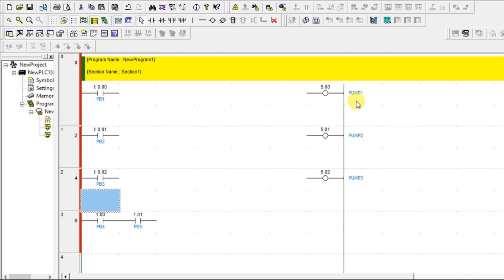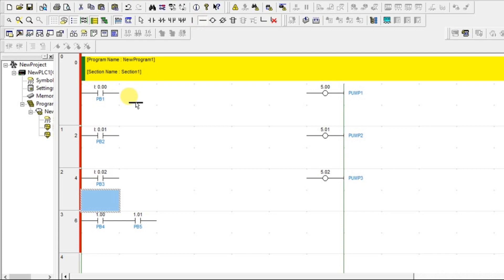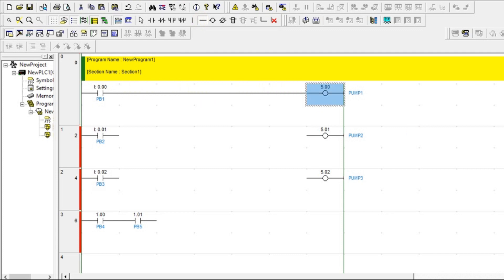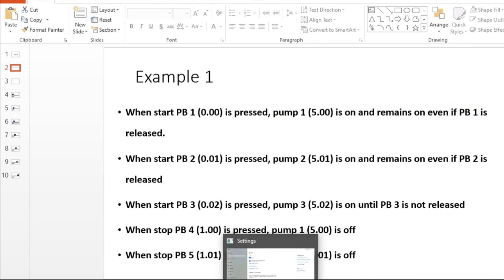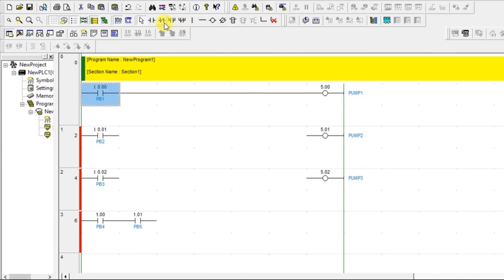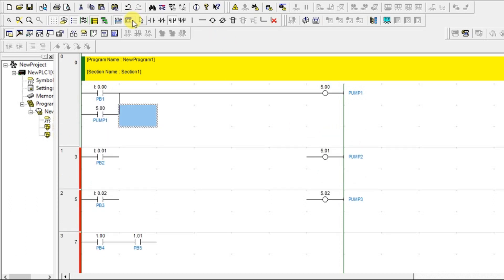The first statement: whenever push button 1 is pressed, pump 1 has to turn on. Since it is pressed and should turn on, it will be a normally open contact. I am connecting directly like this. And since it remains on even if the push button is released, I will put one parallel normally open contact — the address should be the same as pump 1. This is called latching.